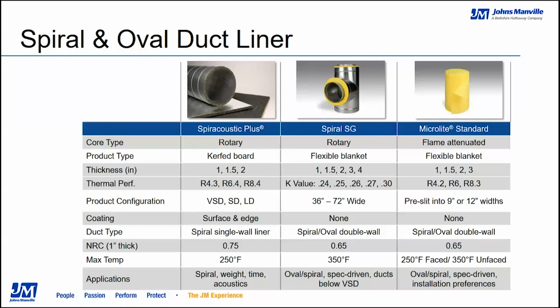The third product, our utilitarian blanket, is the Microlite Standard. One interesting thing is we have the ability to send pre-slit material as little as 9 inches wide, packaged at 9 or 12 inches wide. Some guys use what's called candy cane, where they wrap that spiral pipe, let it spin, and hold that 9-inch wide fiberglass so it candy canes around the inner metal core. It's a nice product we see a lot in double wall applications, especially on fittings, since it's easier to work with a 9-inch or 12-inch wide blanket compared to something 60 or 72 inches wide like the Spiral SG, making fittings easier to fabricate with fewer cuts and a more user-friendly process.